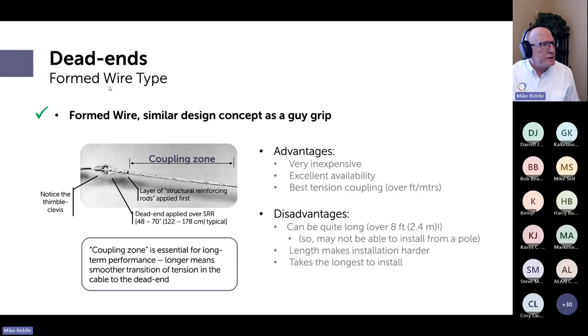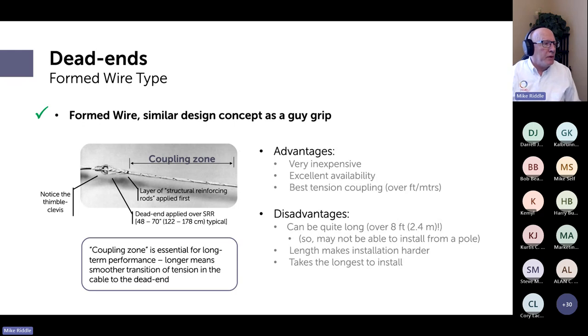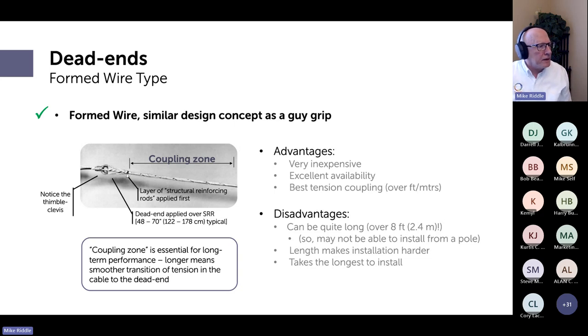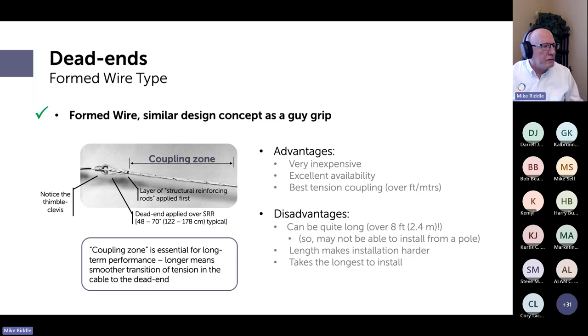First up: dead ends. There are two types. The first is the formed wire type — basically a guy grip. With ADSS, you first apply a layer of structural reinforcing rods, essentially armor rods, over the cable, and then the dead end body goes over that. A thimble keeps the eye of the dead end from collapsing when the cable is under tension.